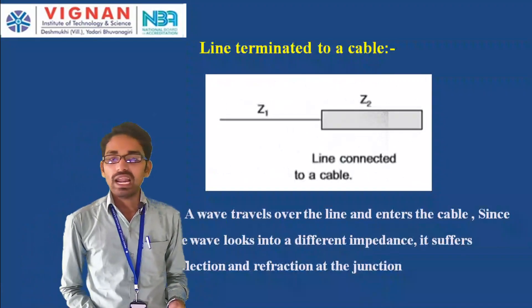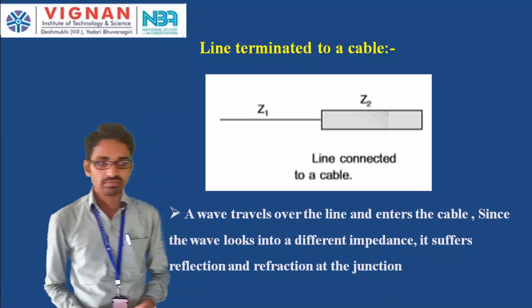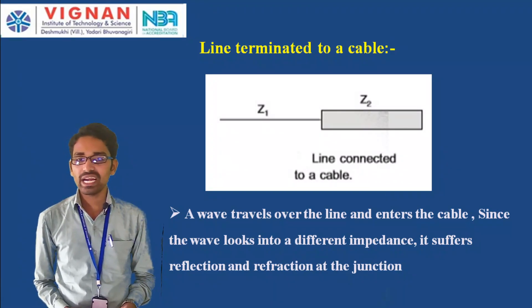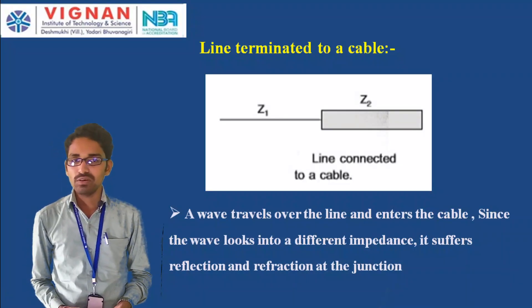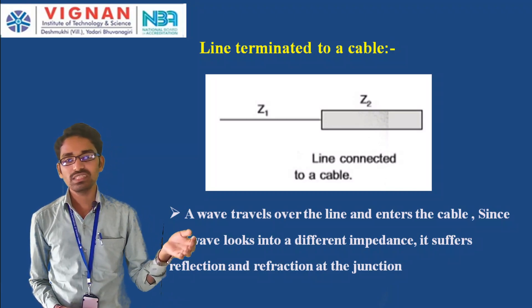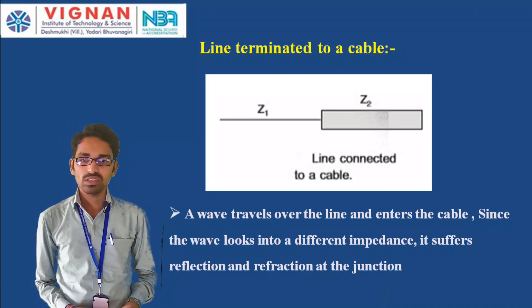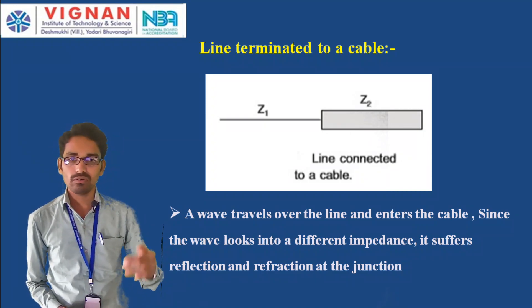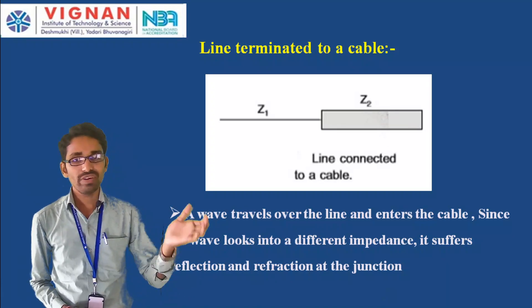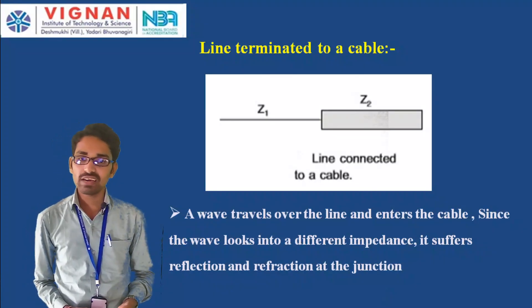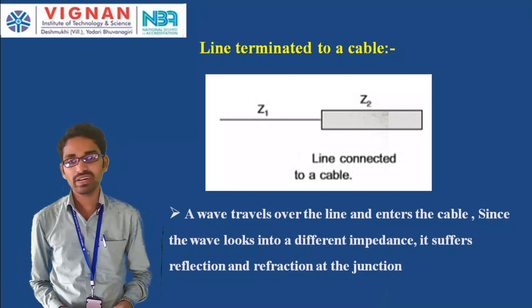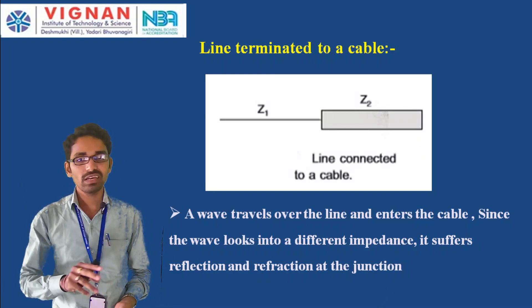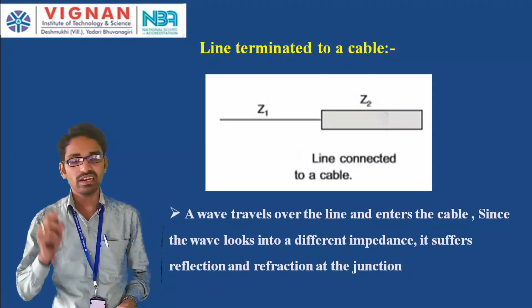The next topic is line terminated to a cable — connecting an overhead line to an underground cable. When the traveling wave on the overhead line enters the cable, it encounters a different impedance because the cable has significant capacitance, resulting in a different surge impedance. Because of this impedance mismatch, the wave suffers reflection and refraction at the junction where the overhead line connects to the underground cable.